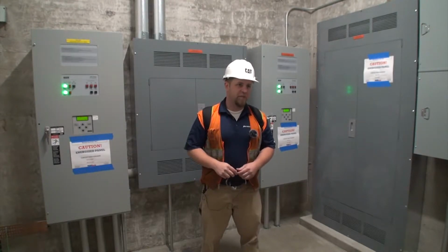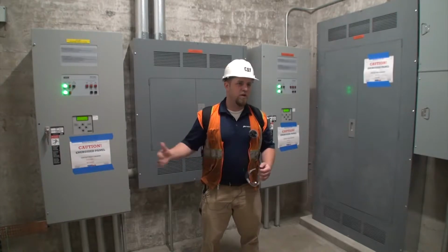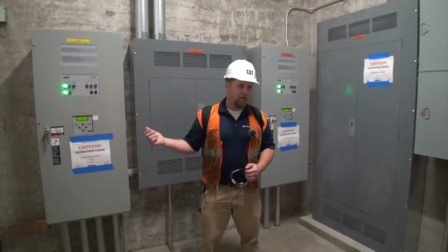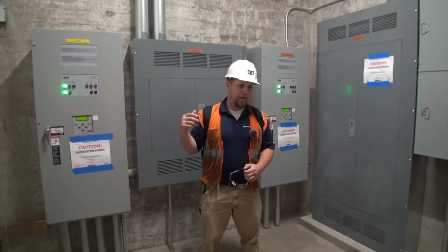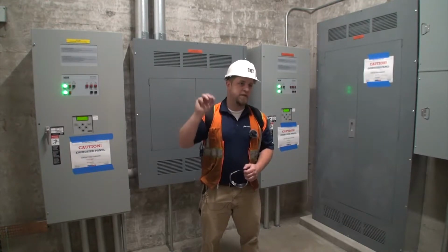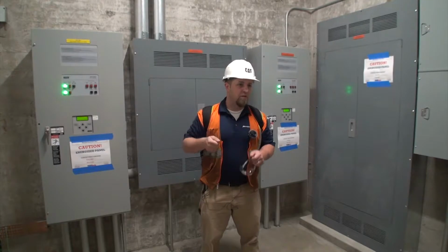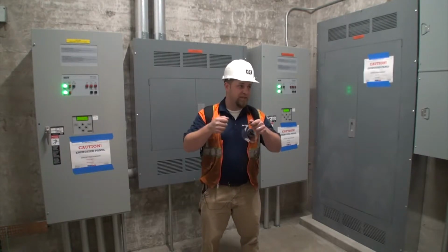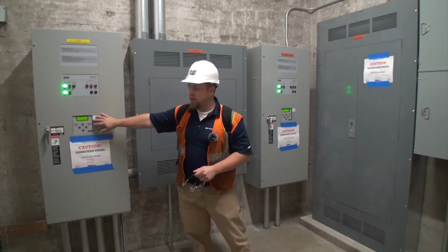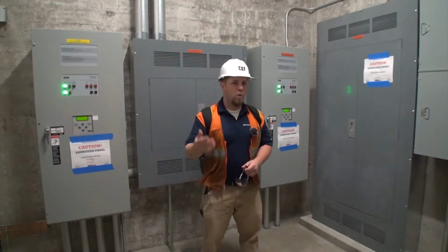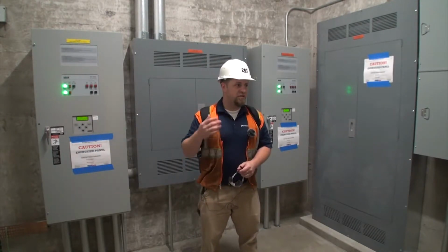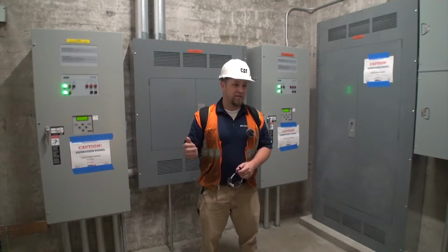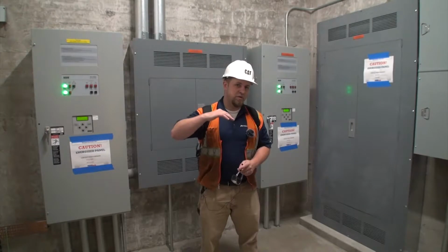To inspect them, you're going to need your arc flash gear, open it up, clean it out. A lot of the time we'll actually test voltage live, hot on both sides, probing both sides to see if what the screen reads matches the actual voltage. That way you can see line to line whether it's right, and also spot what they call a hot leg, or see where your arc chute contacts are.